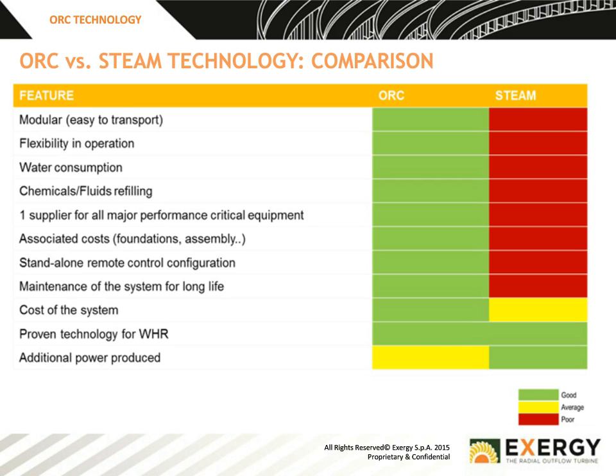Associated costs. ORCs do not need the same scale of foundations. We have typically seen approximately 1/3 of the overall weight of foundations for an ORC system than for a steam turbine plant. And this is just because the ORC turbine is very simple, relatively light, and as such, the foundation requirement is generally less. All of our plants are set up for remote operation, which actually means we operate them and can monitor them from the factory here in Italy.